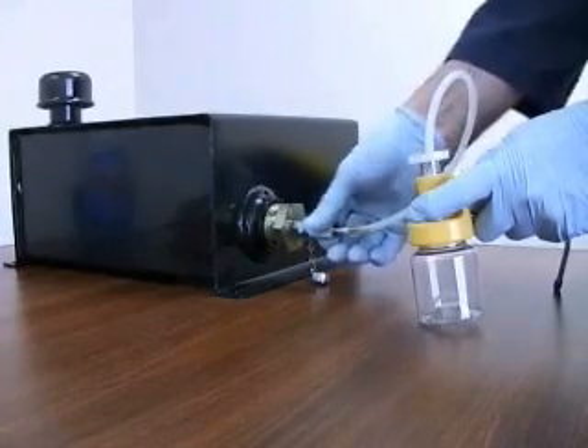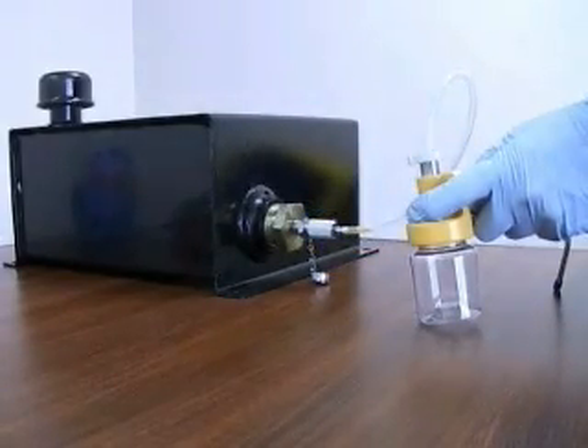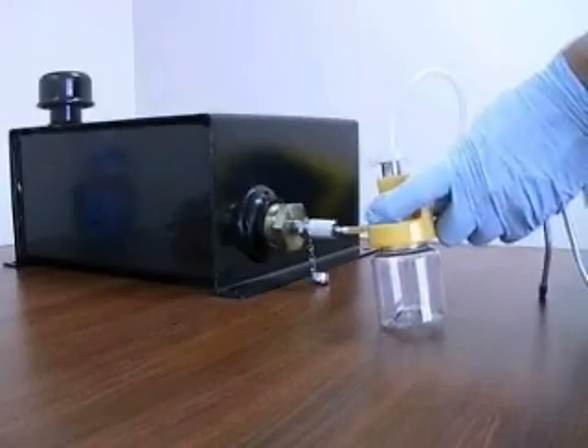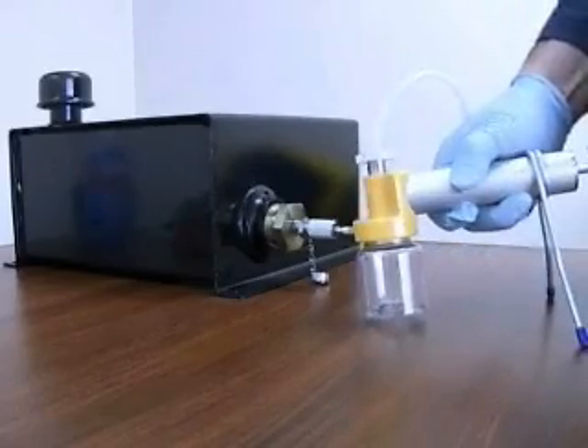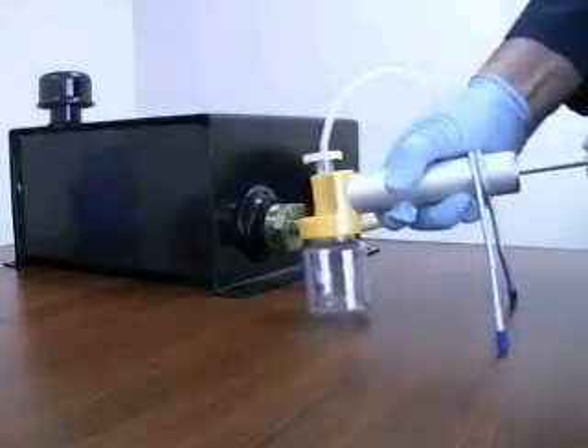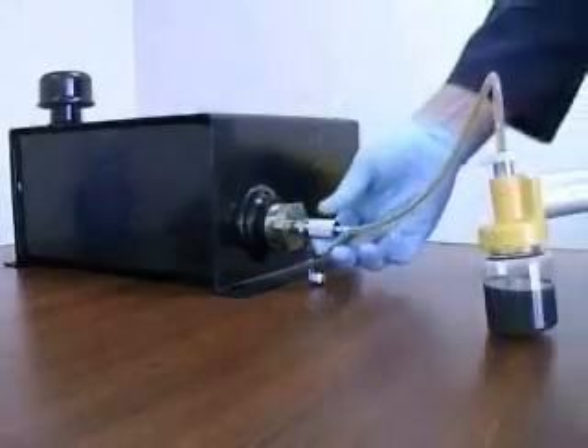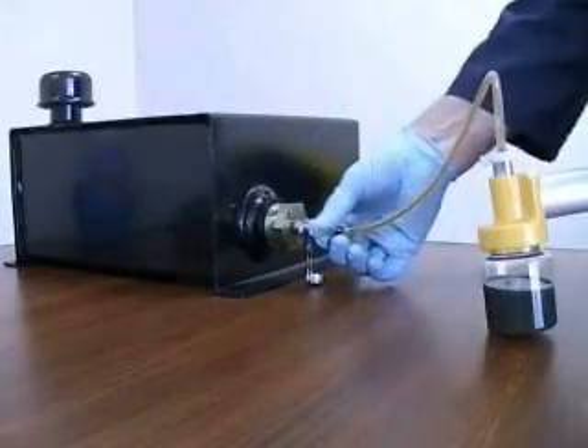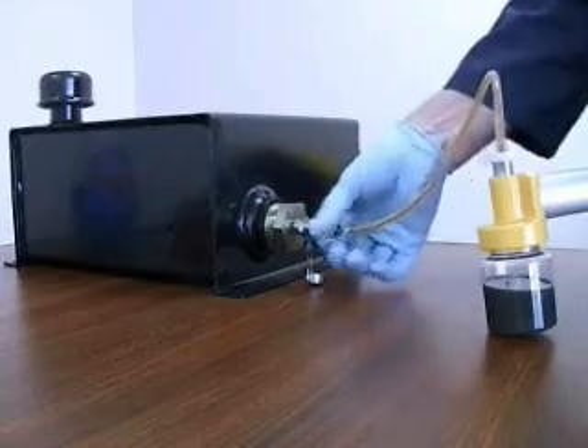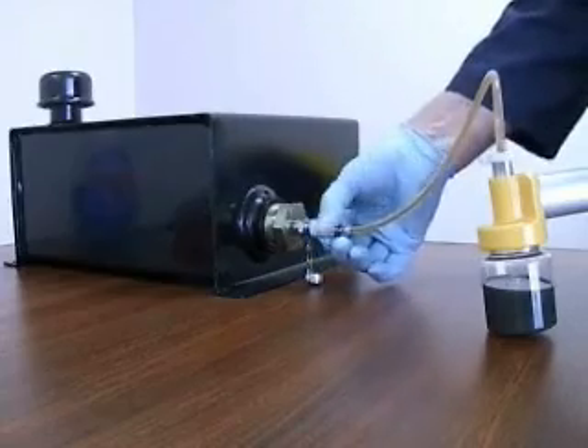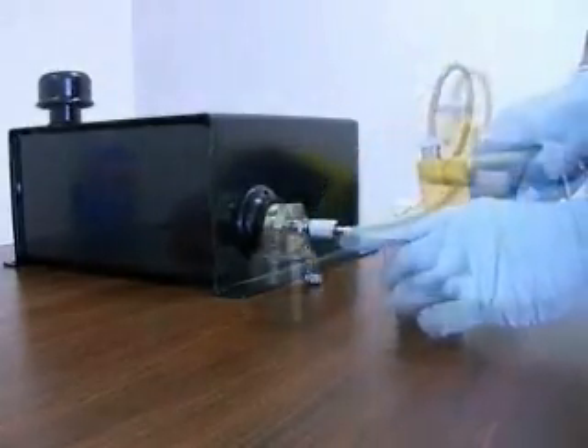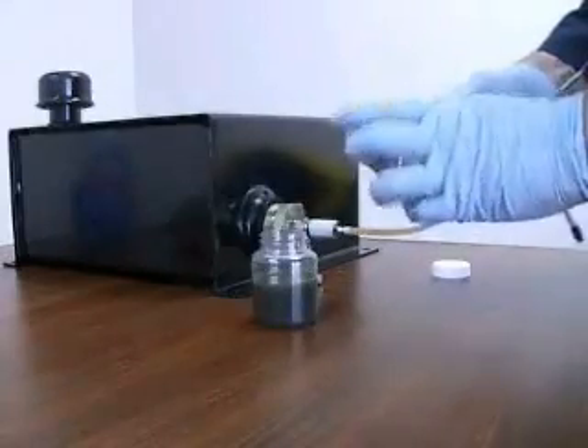Thread the probe fully on the valve, pull the vacuum plunger several times to start the flow, and avoid over-plunging, which may collapse the bottle. When 2 ounces of oil has been collected, unthread the probe approximately 2 turns to stop the flow. This will keep the connection sealed. Remove the purge bottle and thread on the sample bottle.